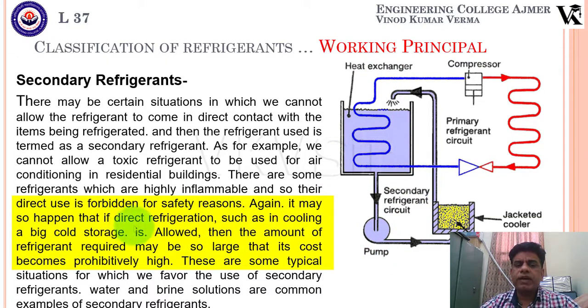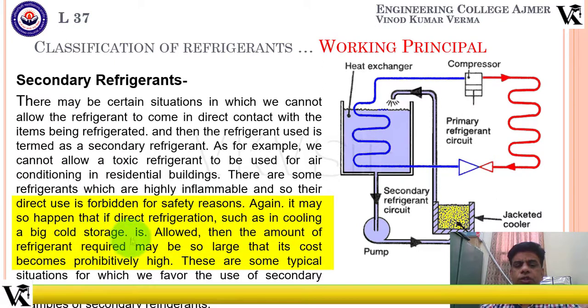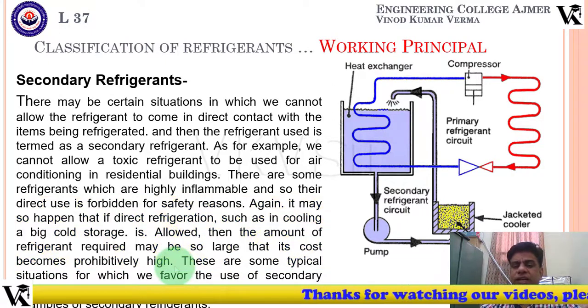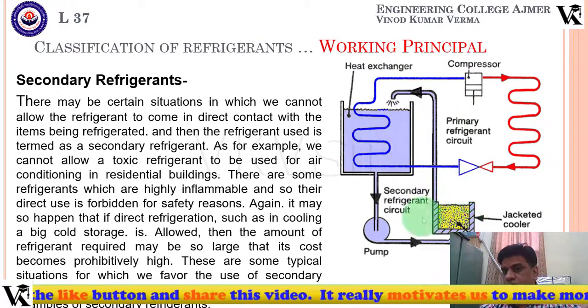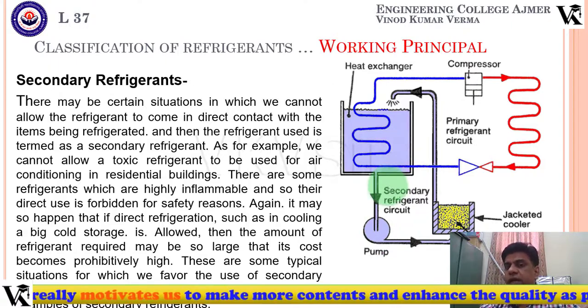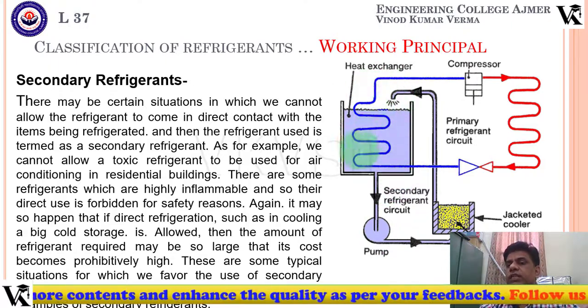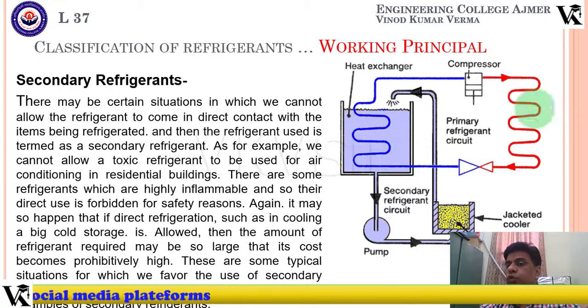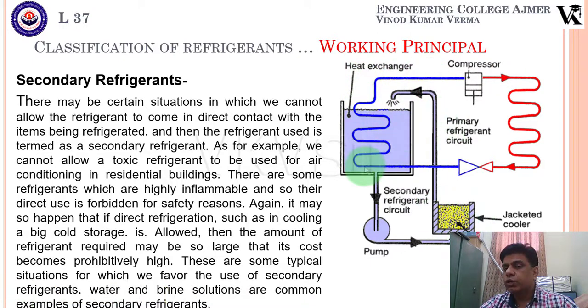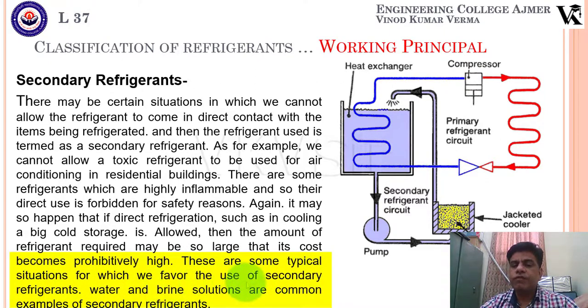Another reason for using secondary refrigerants: if direct refrigeration in a large cold storage requires a very large quantity of refrigerant, its cost may become prohibitively high. In such a case, we can use a highly effective but toxic refrigerant in the primary circuit in smaller quantities, and use a secondary refrigerant for the actual cooling zone. These are typical situations that favor the use of secondary refrigerants.